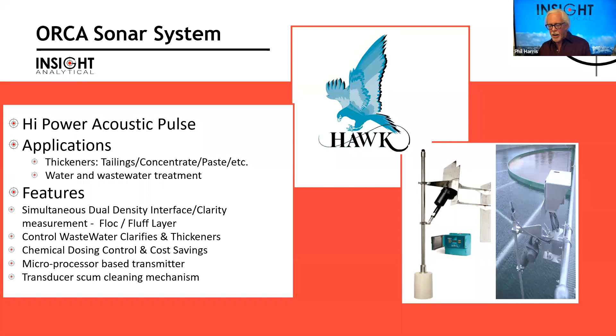We'll have the sensor in there and we get a different speed of sound, with a bounce back from the first place off of that free settling zone. Then we go through what we refer to as a hindered zone, where it's not really liquid and not really solid yet, and we get a bounce back off the compacted zone at the bottom. We can look at the acoustic signals that come back and identify all of those different level points, and if we're adding chemicals to speed up that settling, it allows us to control our injection rates.